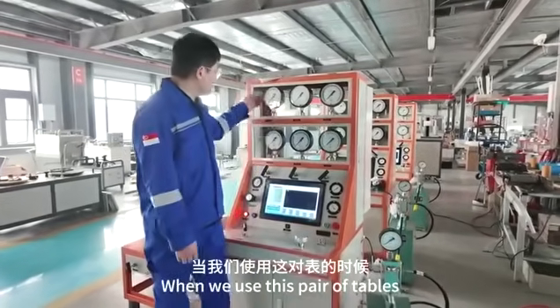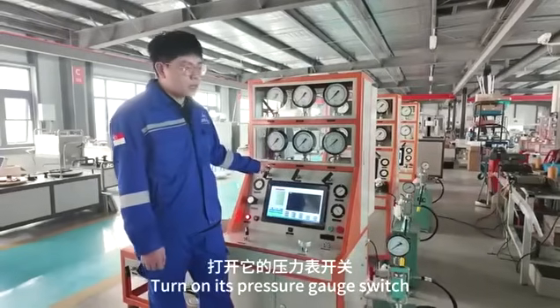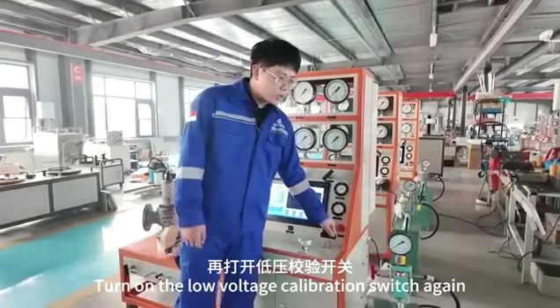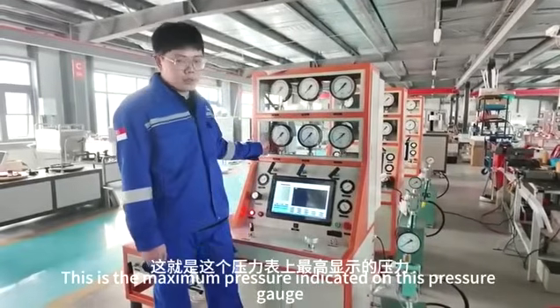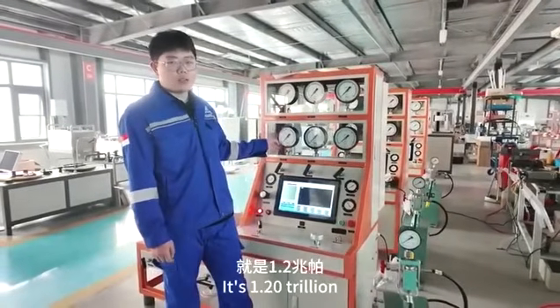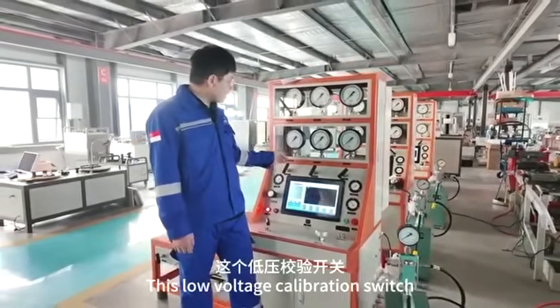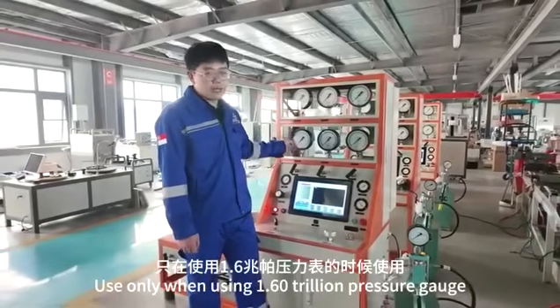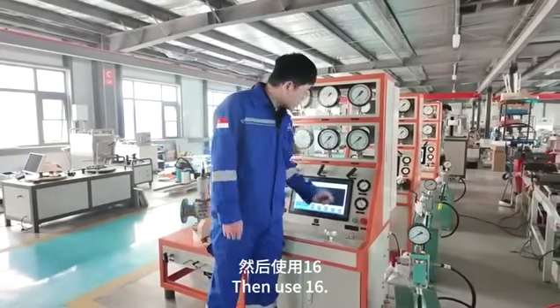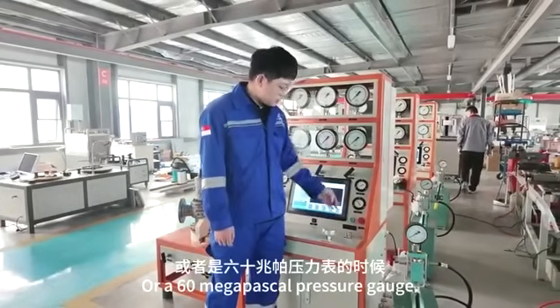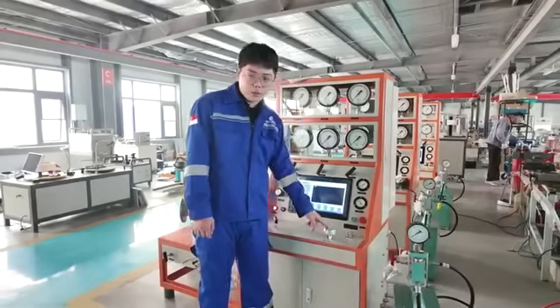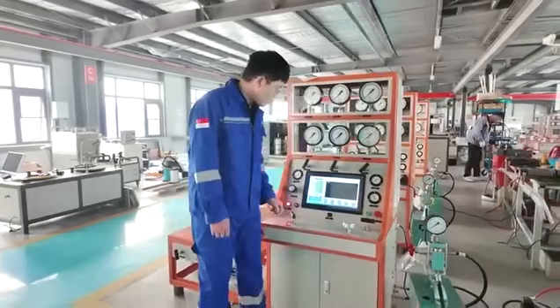When we use this pair of tables, turn on its pressure gauge switch. Turn on the low pressure calibration switch again. This is the maximum pressure indicated on this pressure gauge. It's 1.20 megapascal. This low pressure calibration switch, used only when using 1.60 megapascal pressure gauge. Then use 16 or a 60 megapascal pressure gauge, is to use high pressure or medium pressure. The check switch is this.